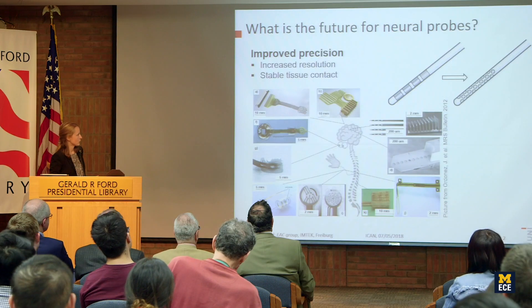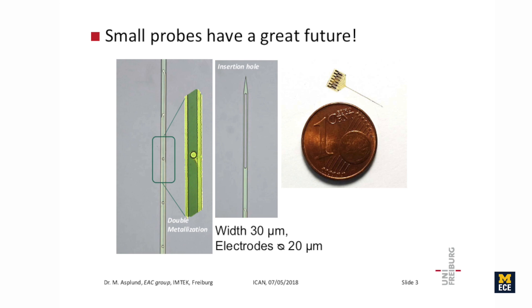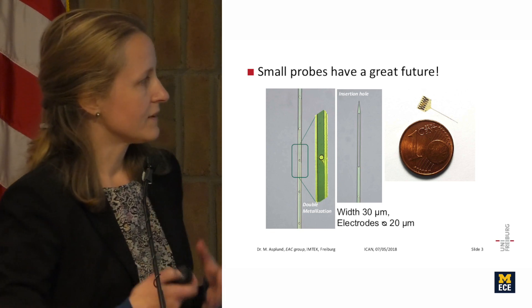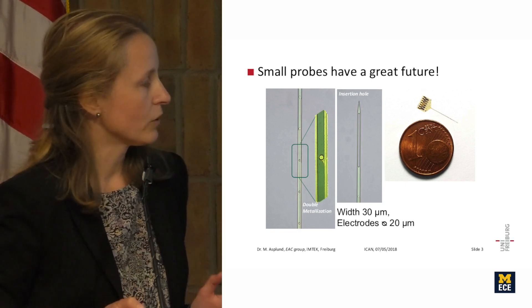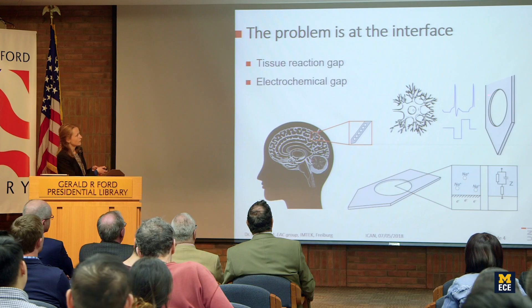Whether we make the complete device smaller or add many more electrode sites representing single channels for more precise interaction with the nervous system, we are going to need very small electrodes. This is one of the smallest polyimide probes I've worked with — a 30-micron-wide polyimide shaft, compared to the typical 500 microns in width, achieved by stacking several layers.